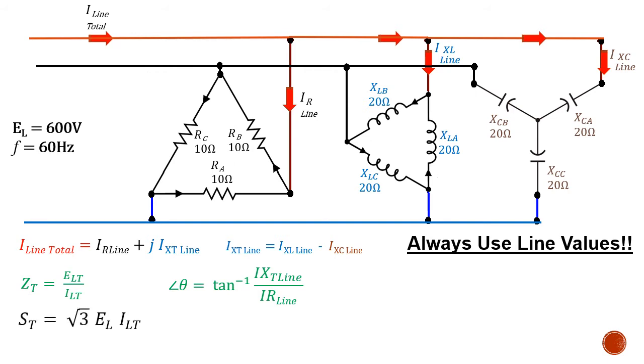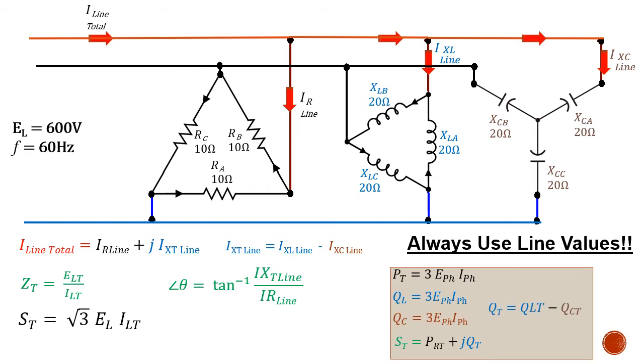Your total apparent power uses the three-phase power formula: root three times E-line times I-line, using your total line current. We can solve for each of the individual powers — resistive, inductive, and capacitive — and vector sum those together, summing the resistive power along with the difference in the reactive powers. I've shown here using three times E-phase times I-phase, but you could also use root three times E-line times I-line for each individual component. Power factor is solved the same way: total true power divided by total apparent power. Power factor equals the cosine of theta, or if you want to find theta, it's the arc cos of the power factor.